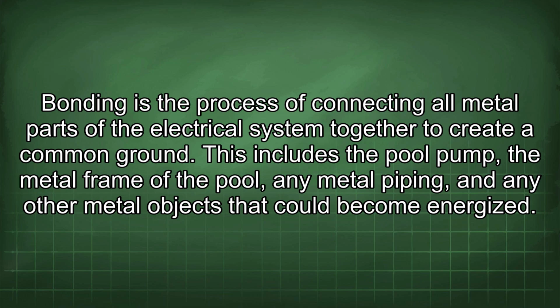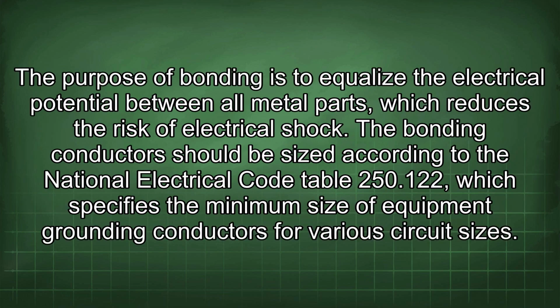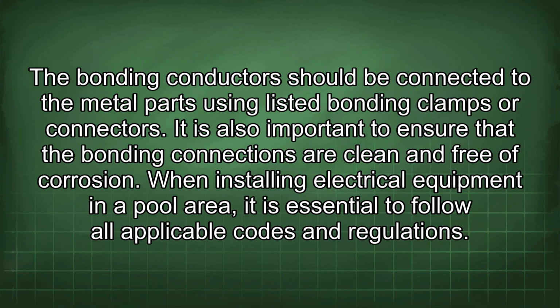Bonding is the process of connecting all metal parts of the electrical system together to create a common ground. This includes the pool pump, the metal frame of the pool, any metal piping, and any other metal objects that could become energized. The purpose of bonding is to equalize the electrical potential between all metal parts, which reduces the risk of electrical shock. The bonding conductors should be sized according to the National Electrical Code Table 250.122, which specifies the minimum size of equipment grounding conductors for various circuit sizes. The bonding conductors should be connected to the metal parts using listed bonding clamps or connectors. It is also important to ensure that the bonding connections are clean and free of corrosion.